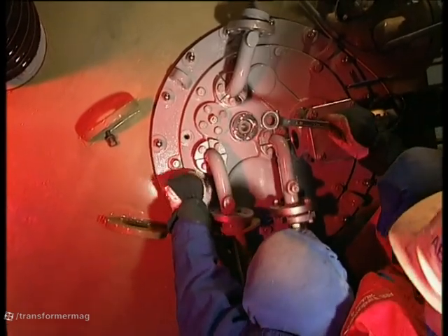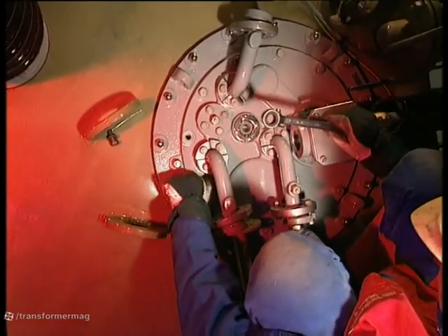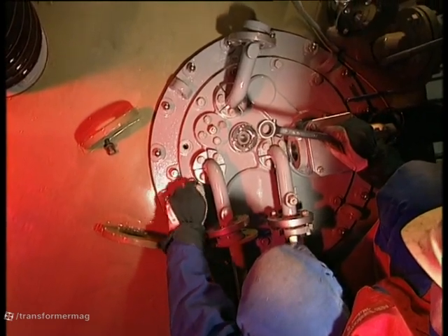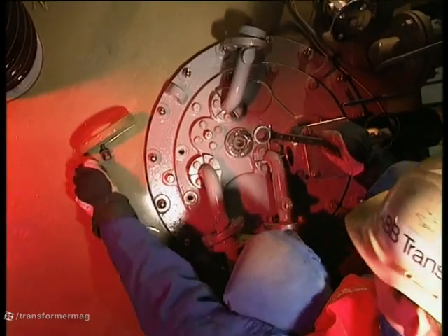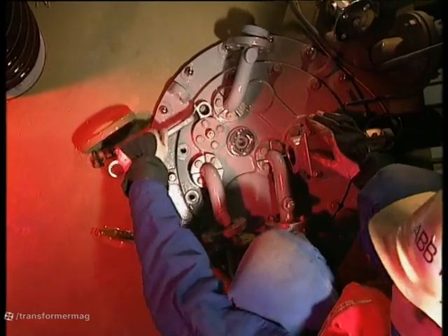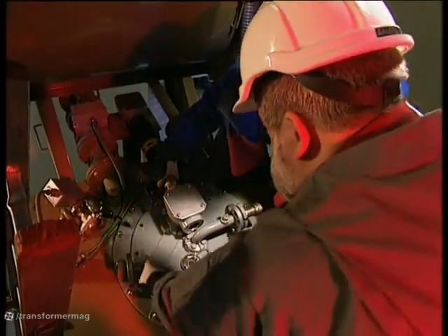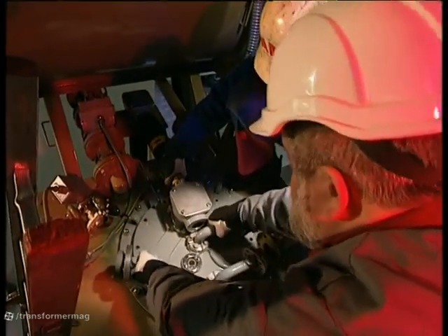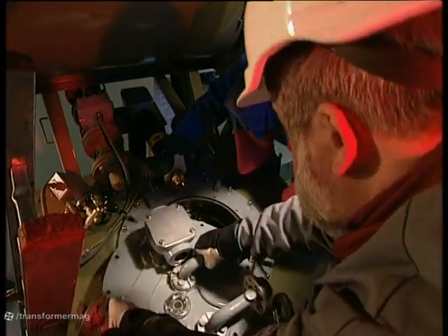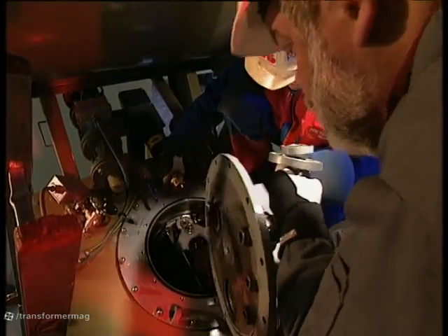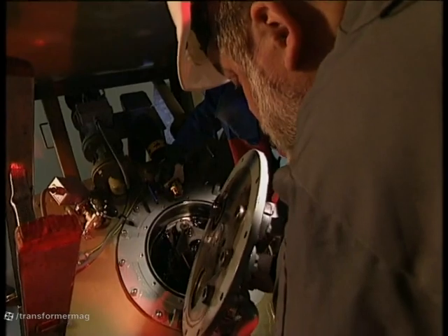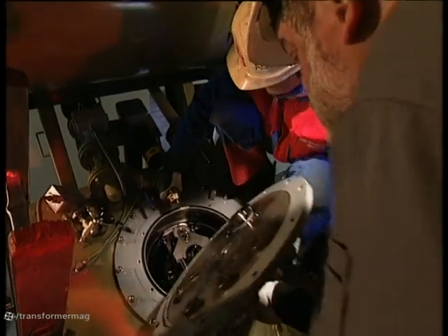You should put every item you remove well away from the tap changer, preferably in jars or boxes. Lift the cover straight up 10 centimeters before moving it sideways. Hold the shaft at the same time so that it does not fall down into the tap changer.